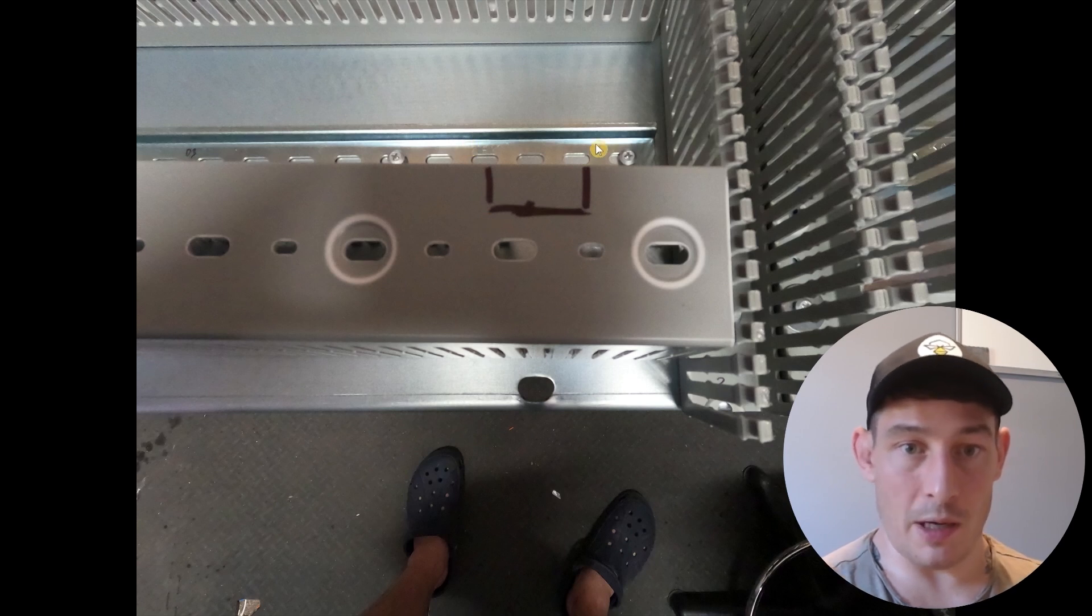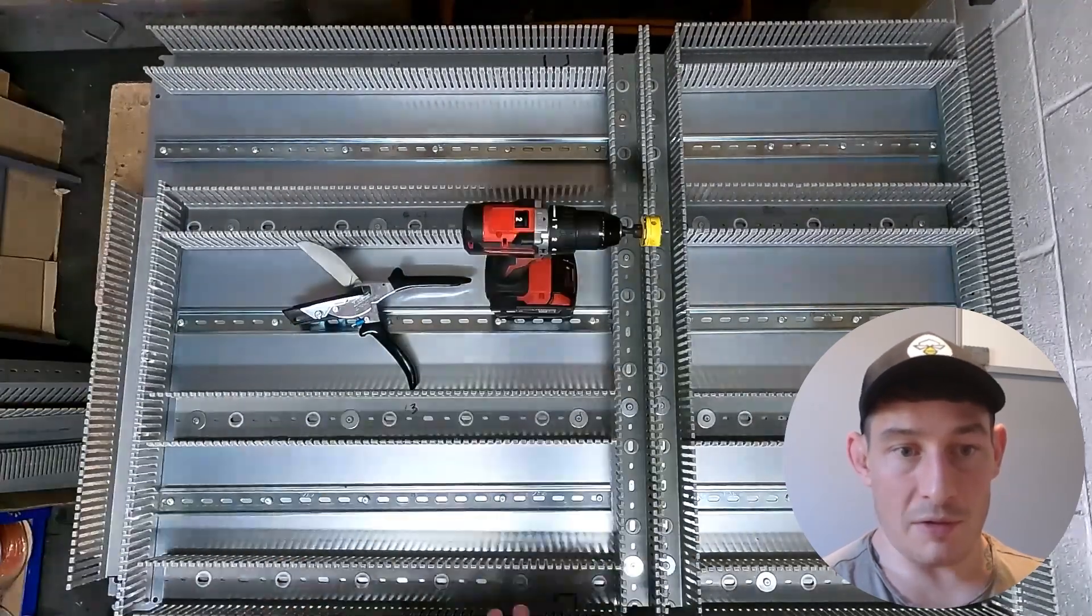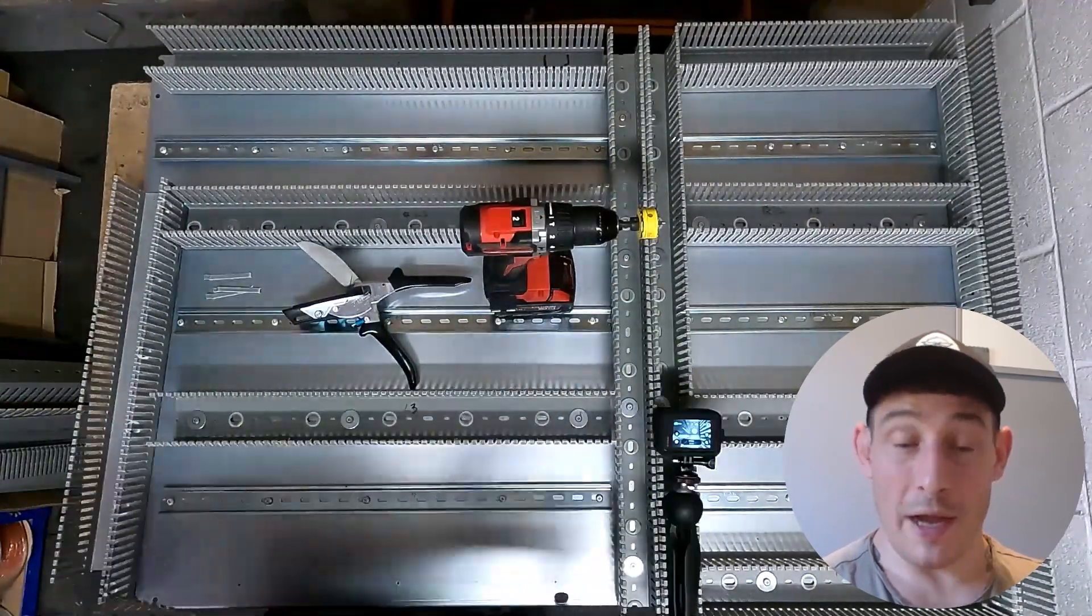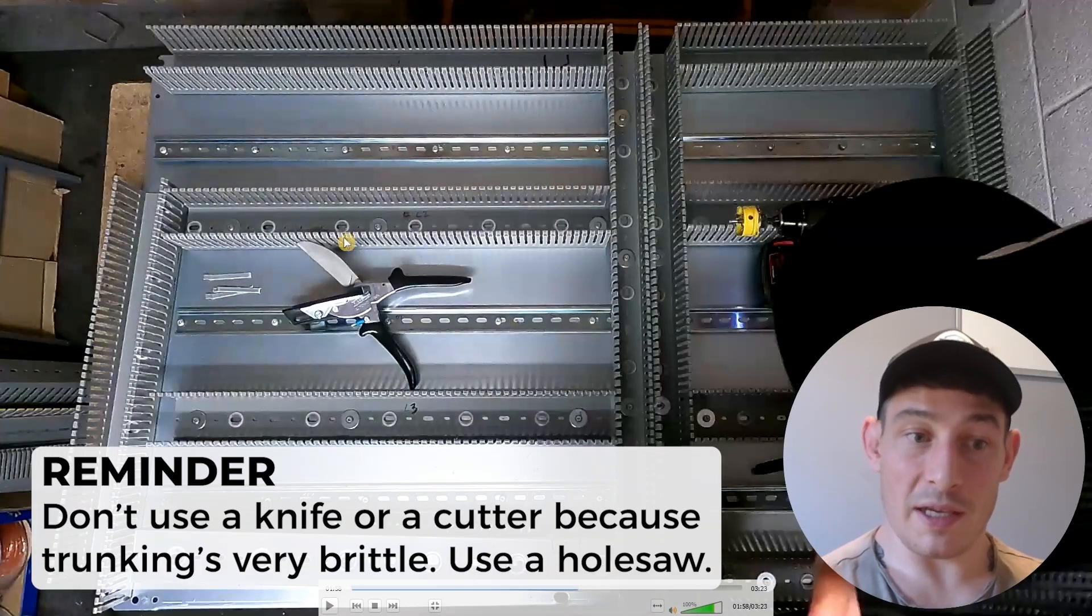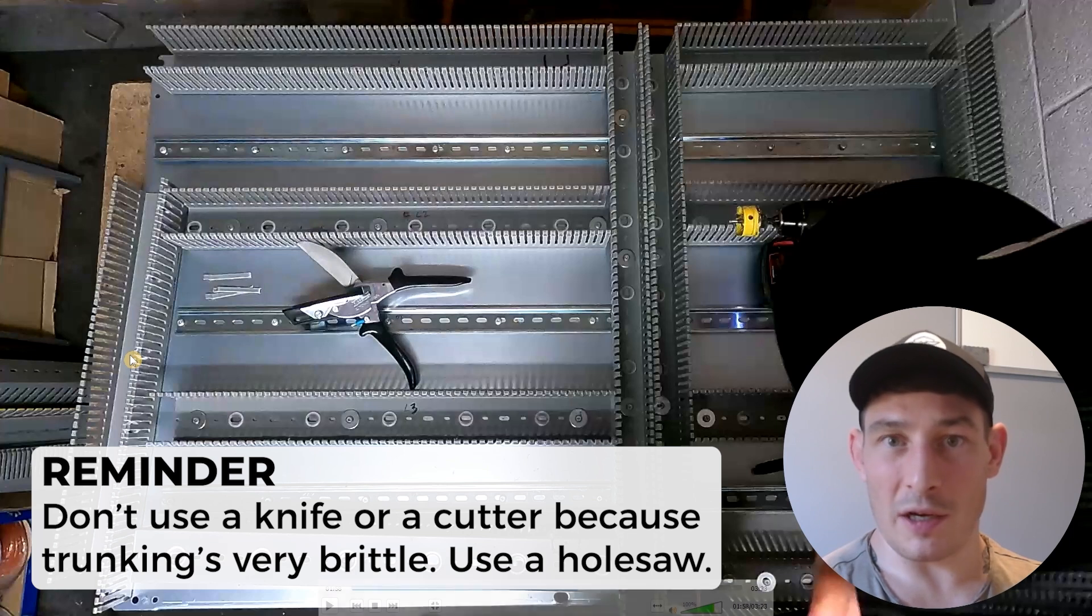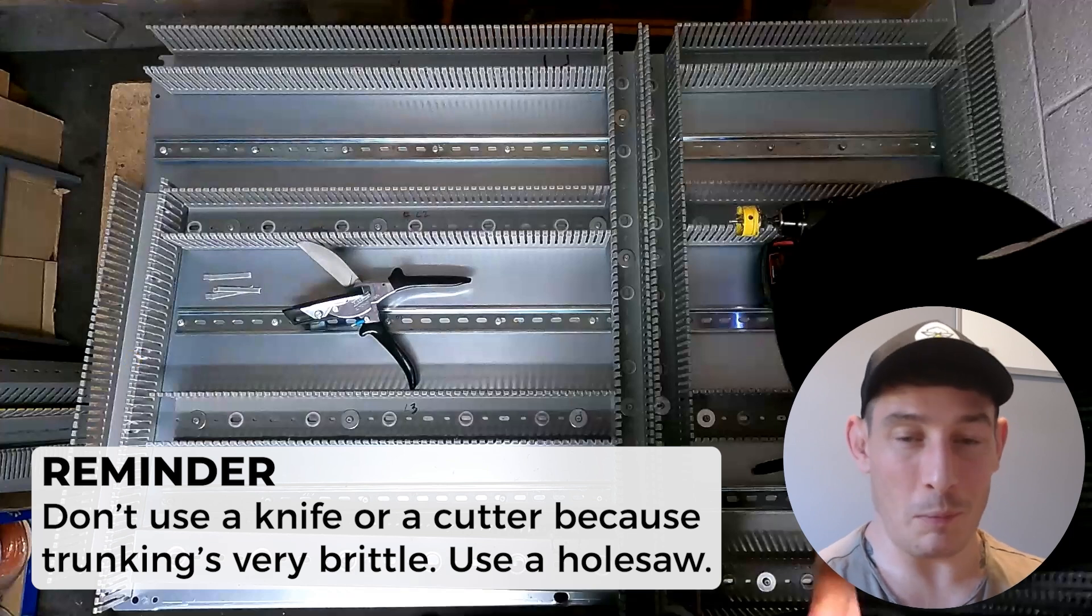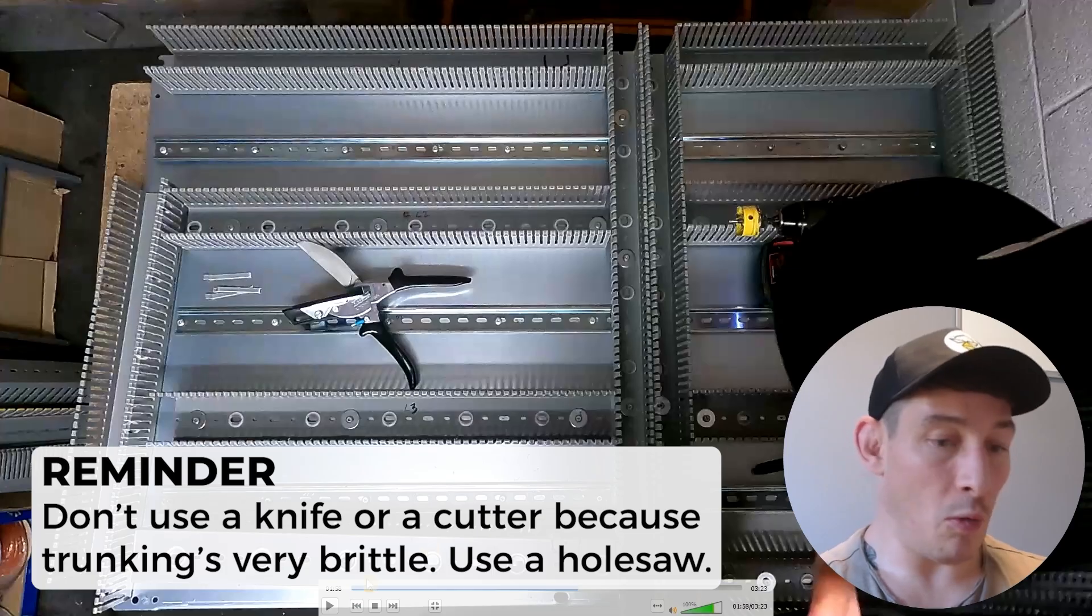And on the underside of that piece of trunking it looks very similar. So going around just doing all of that, and then the best way that I found is not using a knife, not using cutters like this because this trunking is very brittle and can crack in the wrong places. What I found is just use a hole saw.